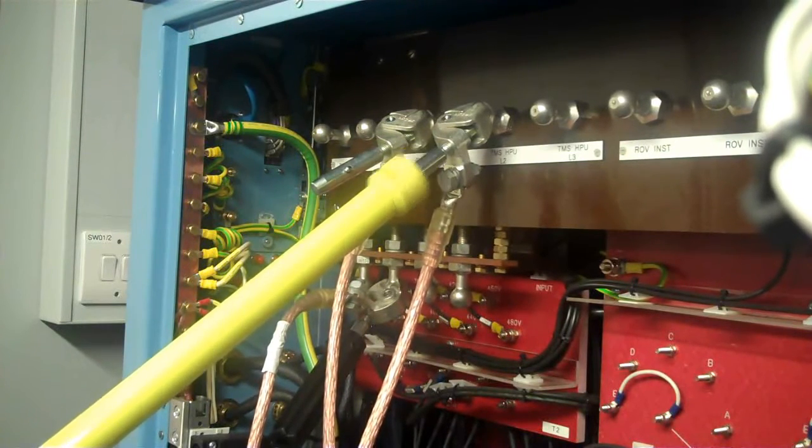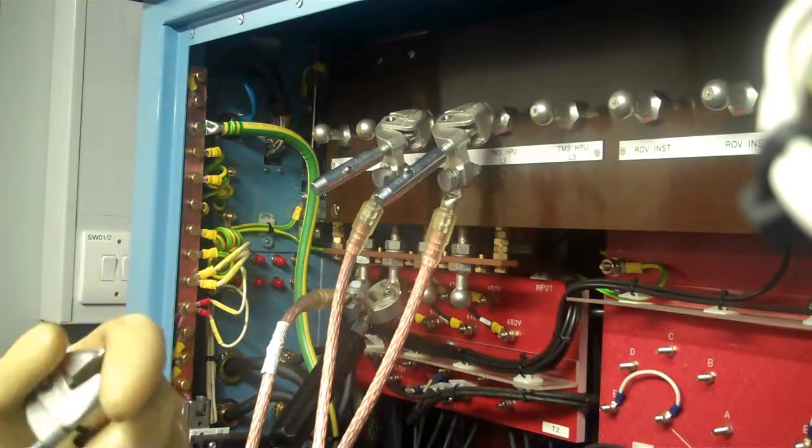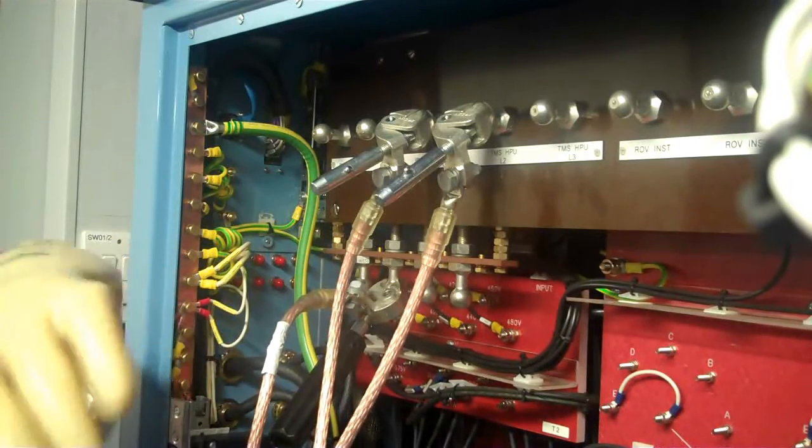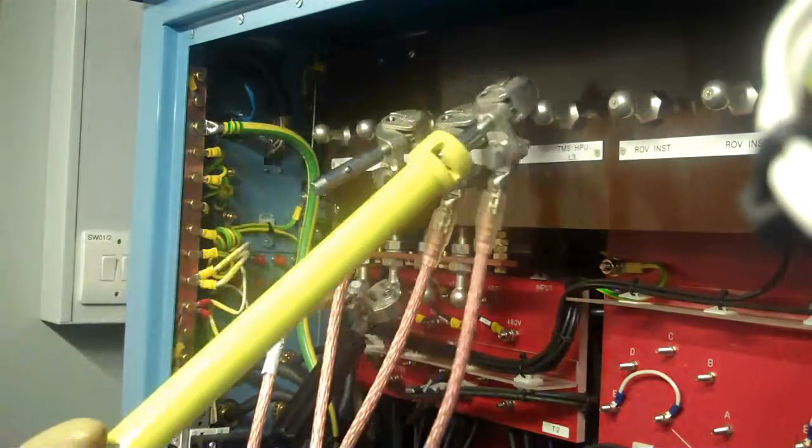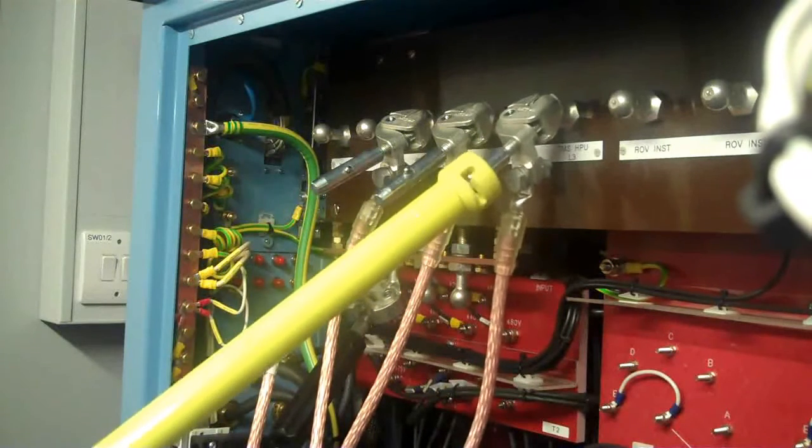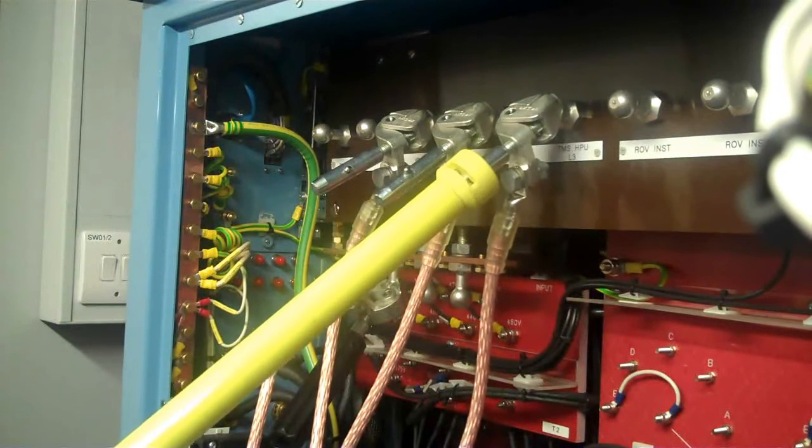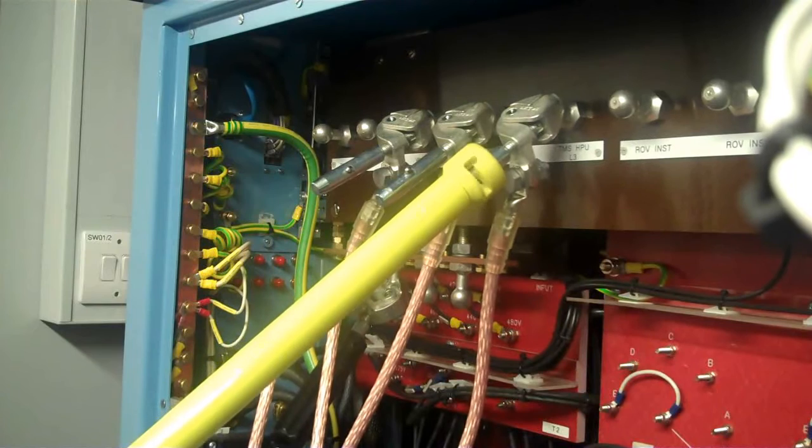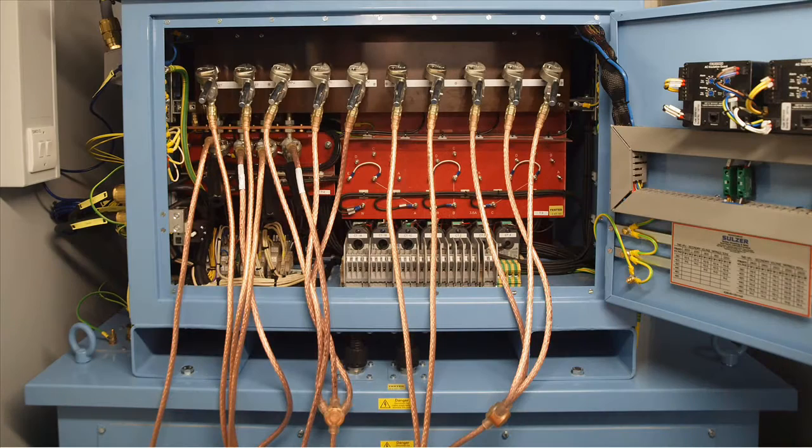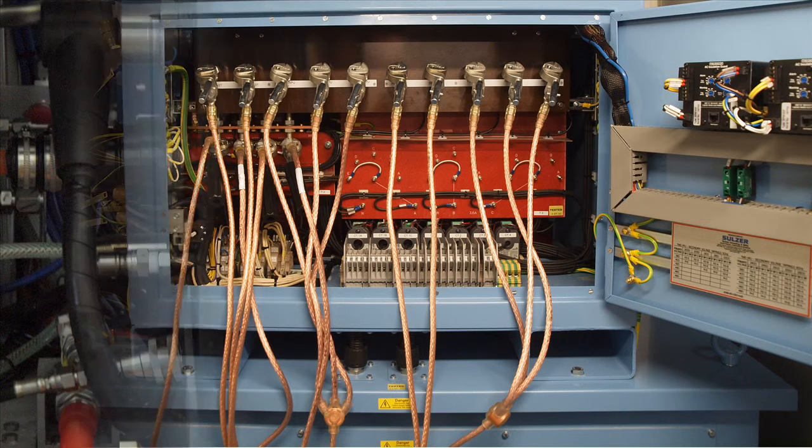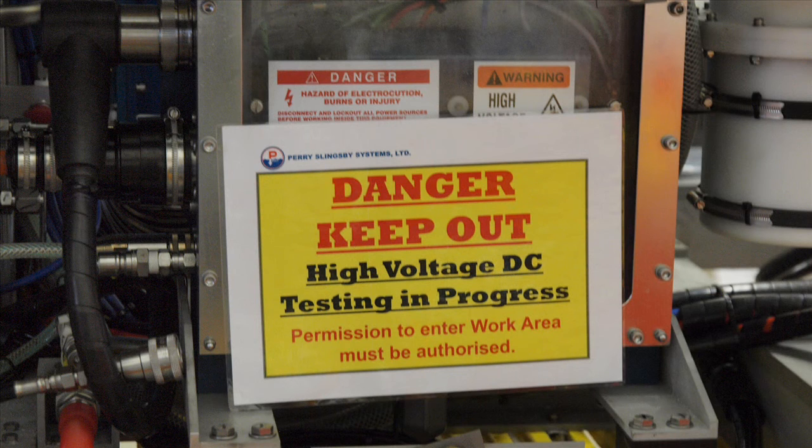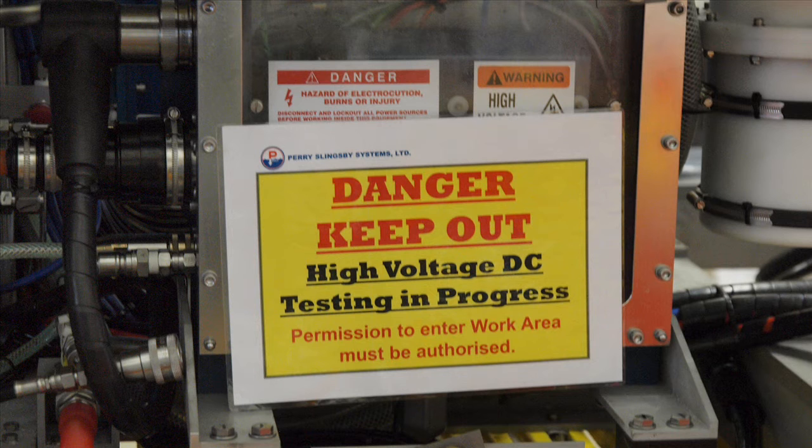It is generally recommended to use a discharge probe to remove any stored charge. Some systems instead use an insulated tool to apply the earth leads. The junction box or transformer is now left open with the leads securely attached. High voltage warning notices are posted at the point where any high voltage work takes place.